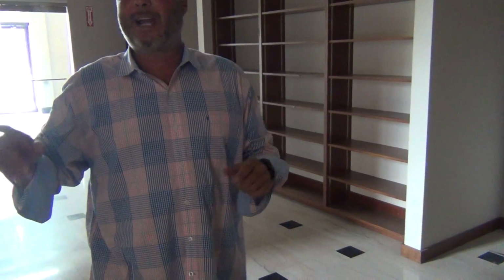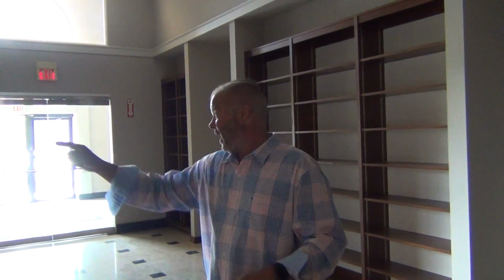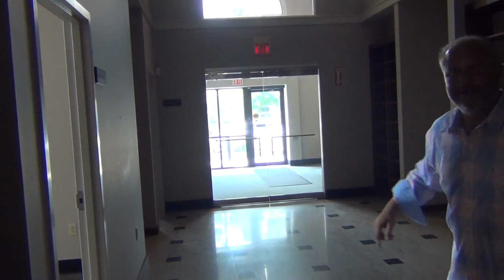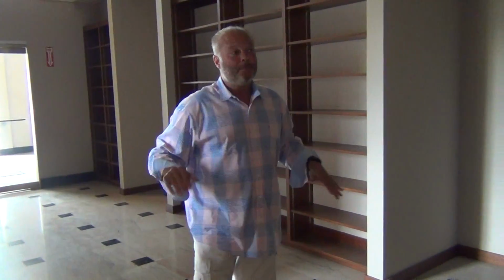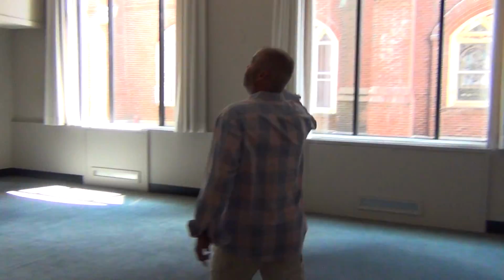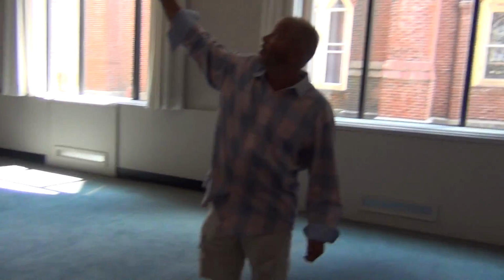By taking down all this ductwork, we need to put the ductwork underneath this floor, cutting holes through the concrete to get it into the floor. Having only 7.5 tons isn't enough to condition this entire room top to bottom, especially with people in it.